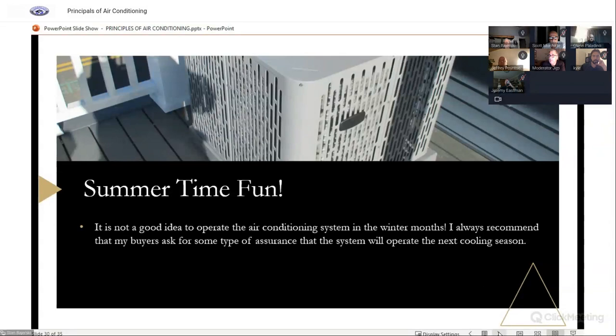Most modern air conditioning systems have what we call a crankcase heater strapped around the base of the compressor. If the system is energized for 24 hours prior, any liquid freon that was in that crankcase will be evaporated by that heater. You can operate the system. It'll turn on and probably not be damaged, but it's not really going to cool. So why even care about that in the wintertime? If we can't operate it, and that's the general rule of thumb, then you write that in the report. I say that some assurance should be made that the system is going to operate in the next cooling season. But I know for a fact that that doesn't happen all the time.